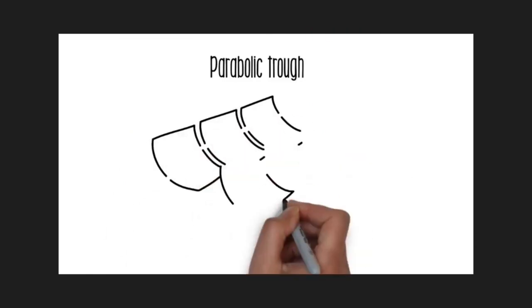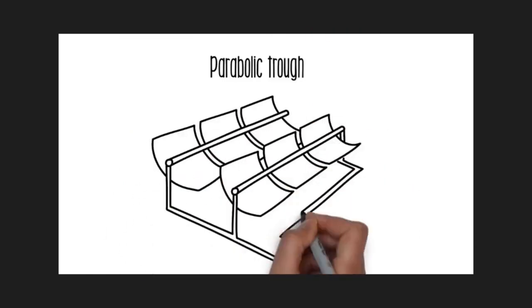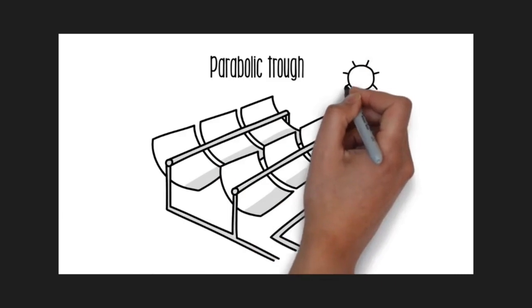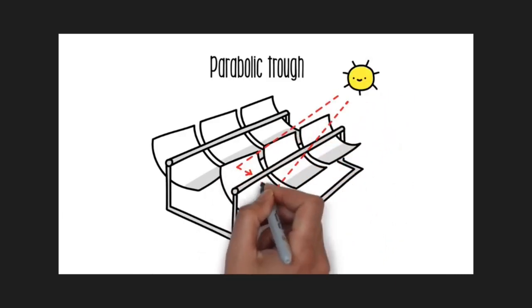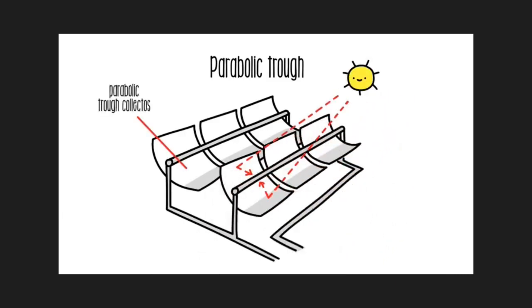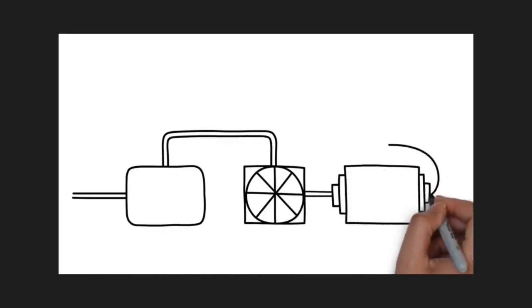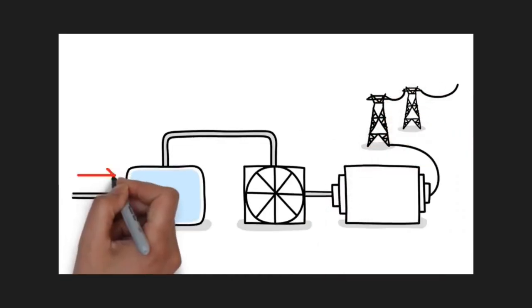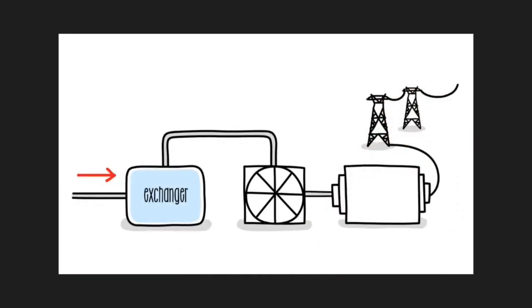In parabolic trough technology, mirrors are used to reflect and concentrate solar radiation onto a pipe located in the focal line. Inside the tube, a thermal fluid is heated to nearly 400 degrees Celsius. Then in an exchanger, it transfers its heat to the water stored there and transforms it into steam. The steam drives a turbine connected to a generator to produce electricity, then is cooled down to start the process again.